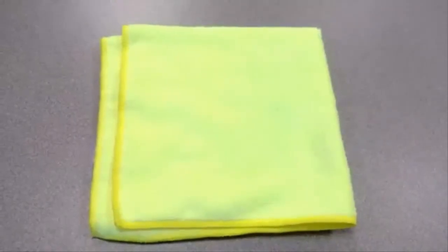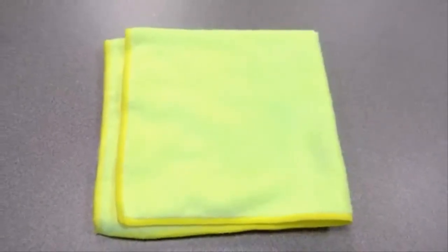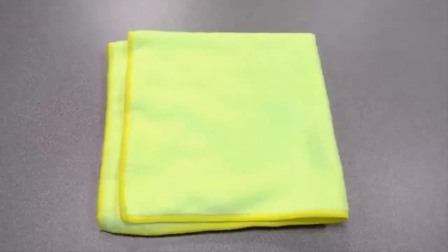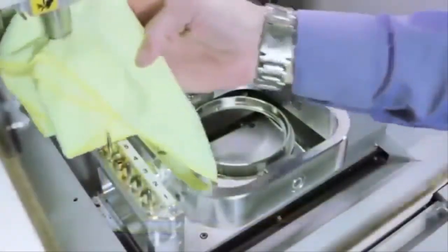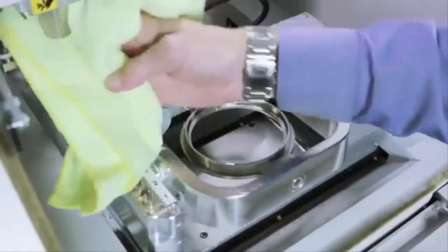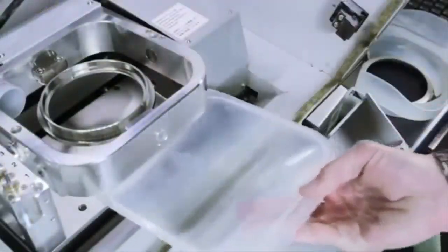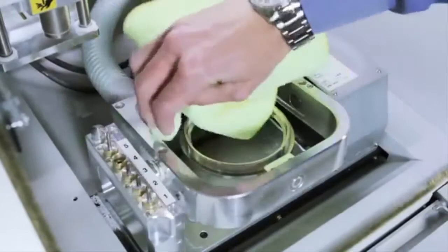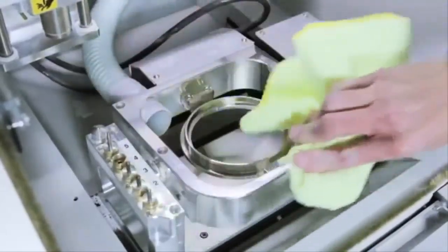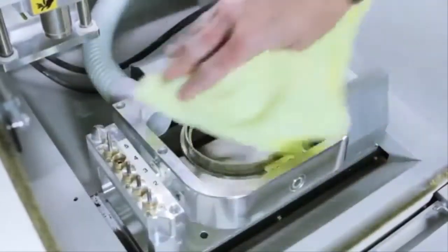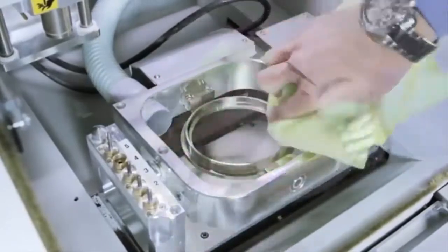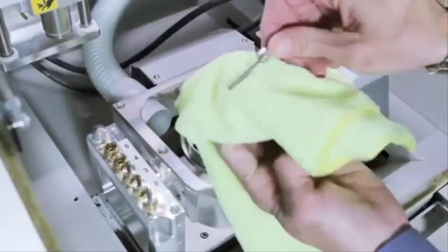Final cleaning of the internal areas of the DWX-50 should be done with a dry, soft, lint-free cloth. Begin by wiping down the fixture, ATC, spindle, calibration pin, and dust capsule. Be sure to clean the small pockets as well. Any tiny pieces of material that remain may possibly interfere with the calibration pin during the detection process.